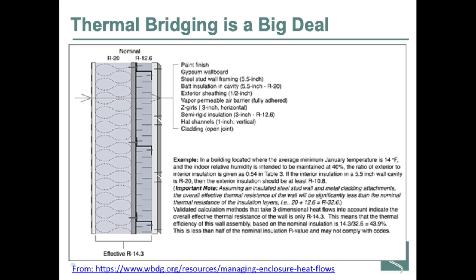I did a lot of consulting with HUD, visiting Indian reservations to look at mold and moisture problems. I can show you pictures of mold forming 16 inches on center at wall-to-ceiling junctions, where you've got two top plates and a low-heel truss sitting up there, in cold climates. Those spots got very cold—we'd measure the wall temperature where the insulation was, and it would be 10 to 12 degrees warmer than up where the low-heel trusses sat, because you just couldn't get much insulation up in there. With exterior vents letting air into the attic, those spots on the wall were colder than the rest. Moisture in the air seeks out cold areas to condense on, so those 16-inch-on-center spots where the trusses hit the top of the wall were the first places mold would form—all due to thermal bridging.